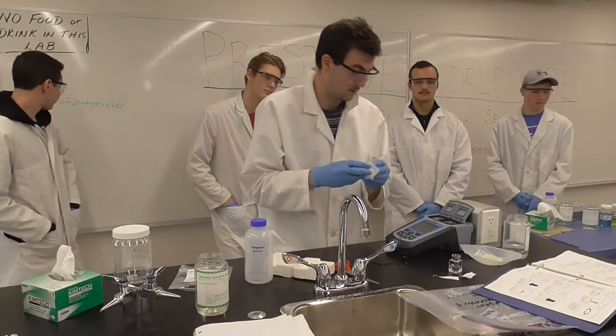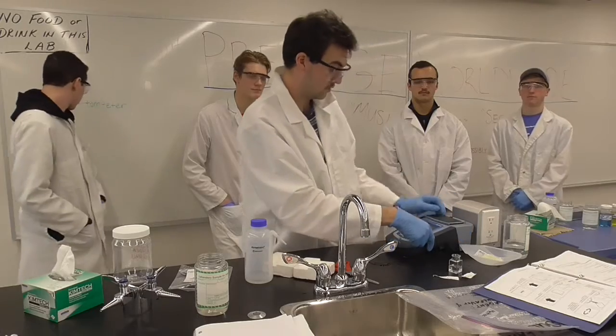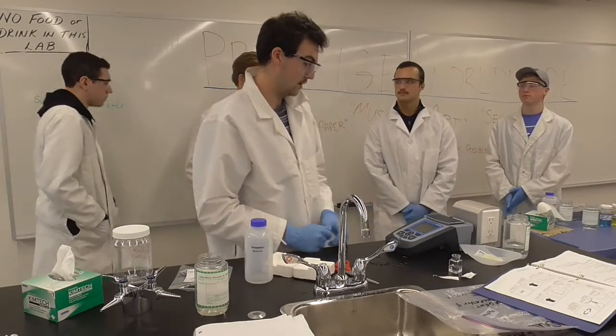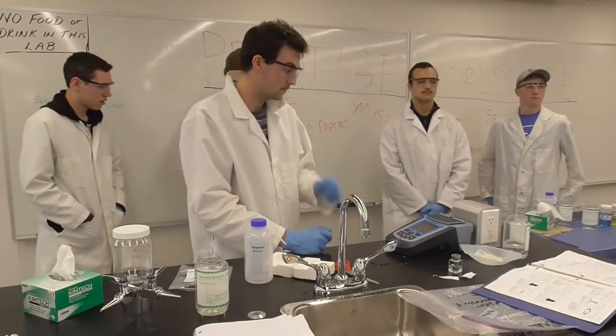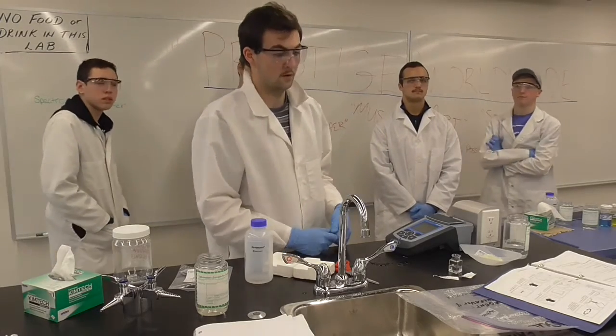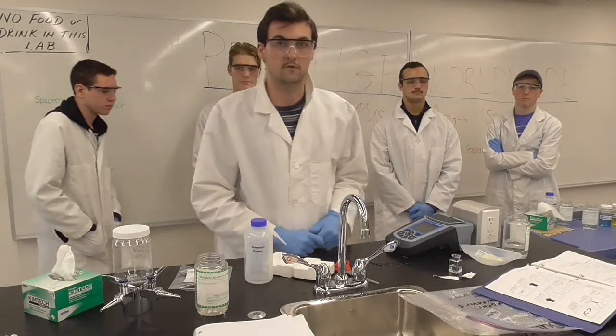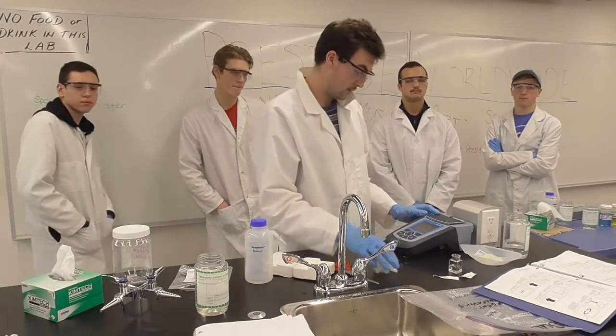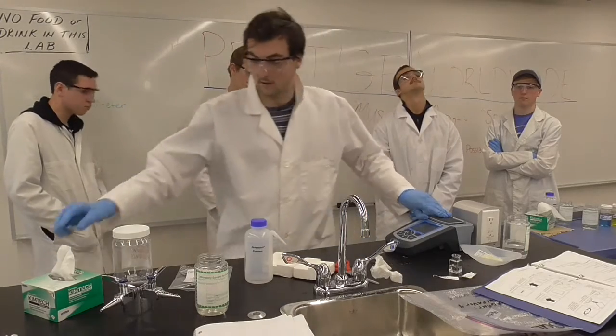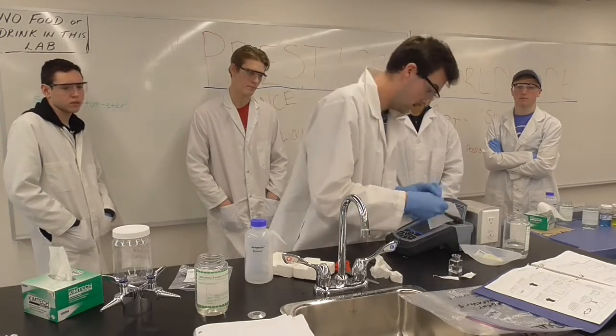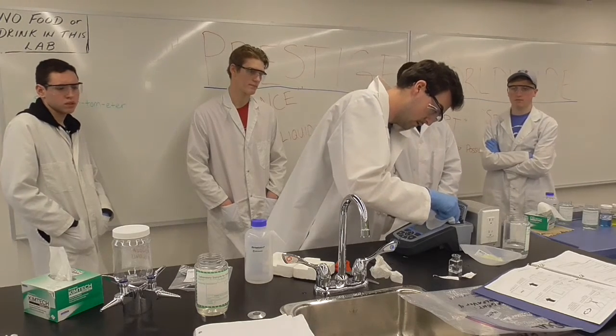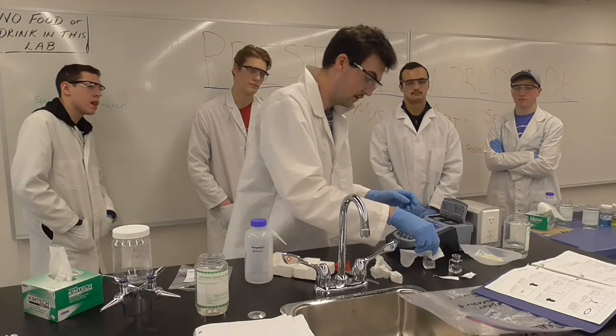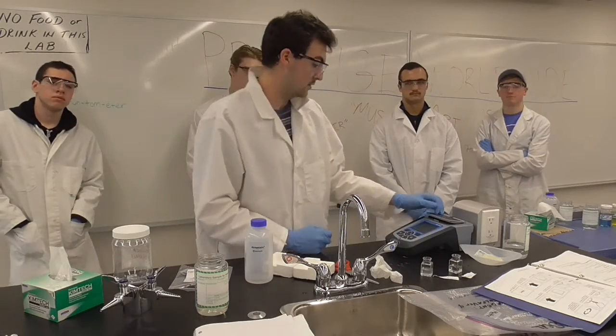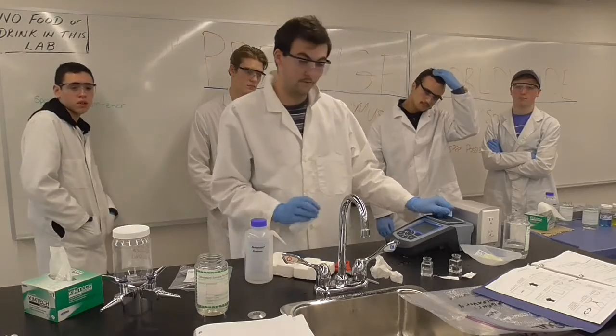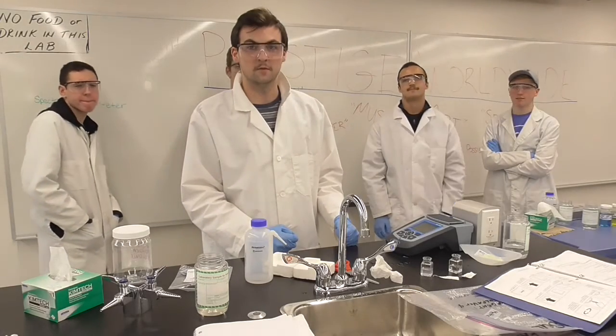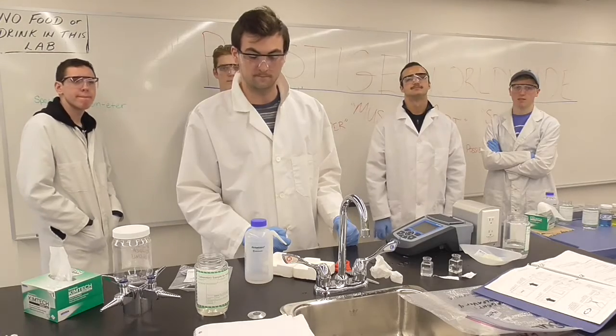Take that off too. Shut that, and then you just click read. It may take a minute or two. Also, our method number for our sulfate is 8051. Oh, and we're done. So we just open this, take another Kimwipe, grab a look at that. There we go. That's out, put that back. And our reading is 16 milligrams per liter of sulfate. So we have 16 milligrams per liter of sulfate in our tap water in this lab.